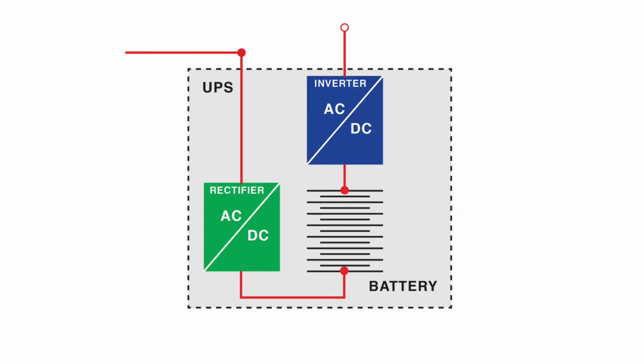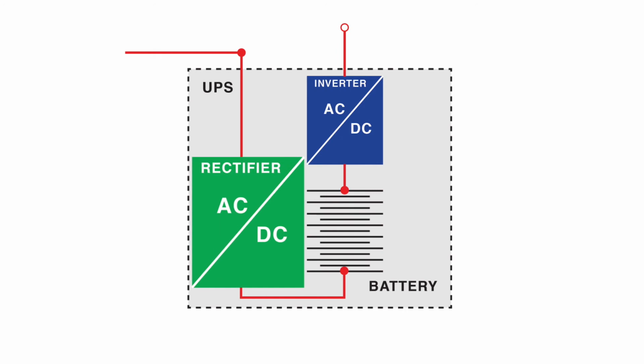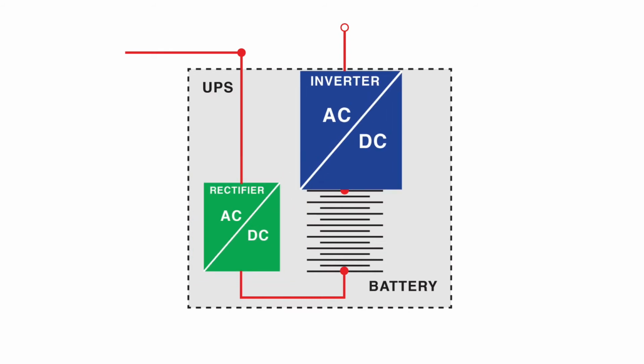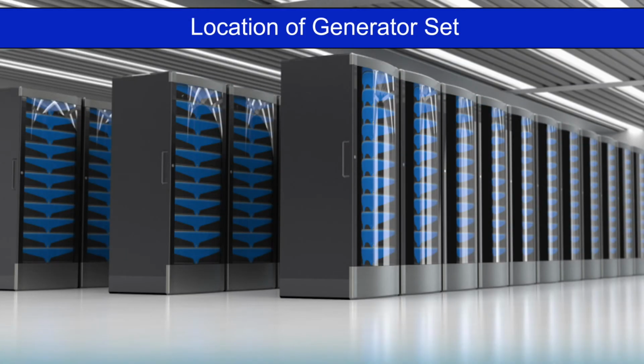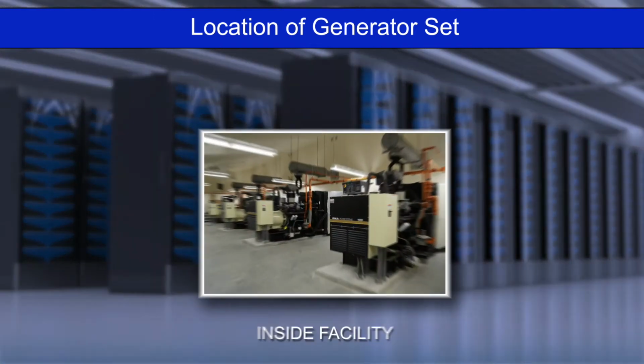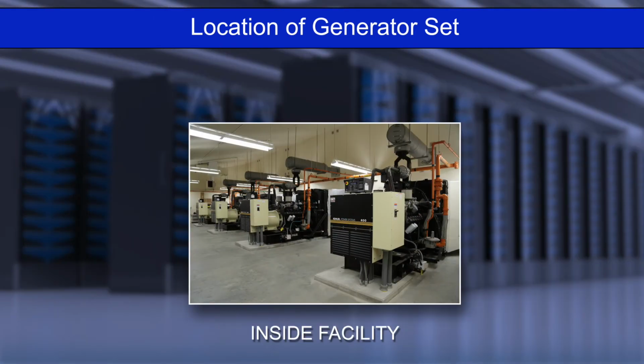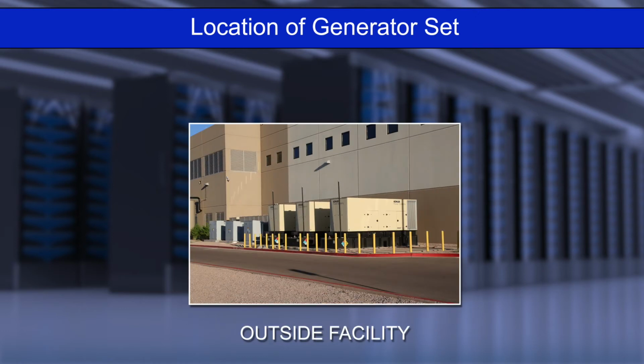Electrical UPS systems store power in batteries. Rectifiers convert AC power to DC to maintain the batteries in a fully charged state, and inverters convert DC power to AC load power. The location of the data center generator will dictate whether the unit is supplied in an open or closed configuration. Whether the generator system is supplied in an open configuration for installing within the building will depend on the individual application, or fully self-contained in an enclosure for outside installation.